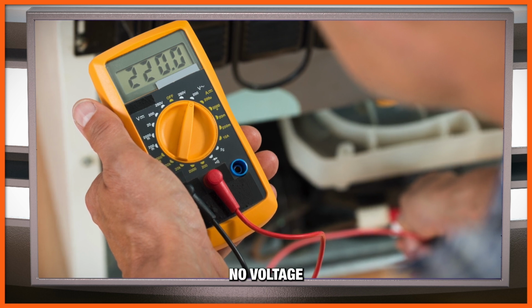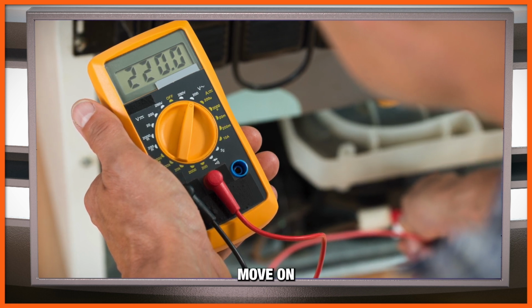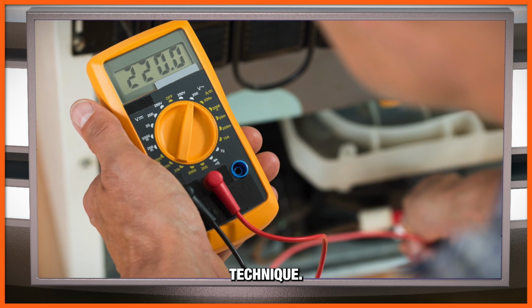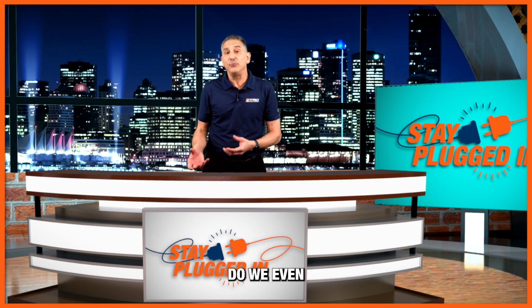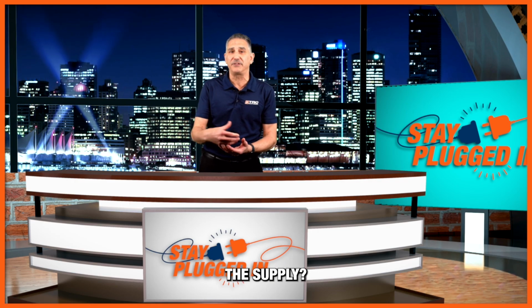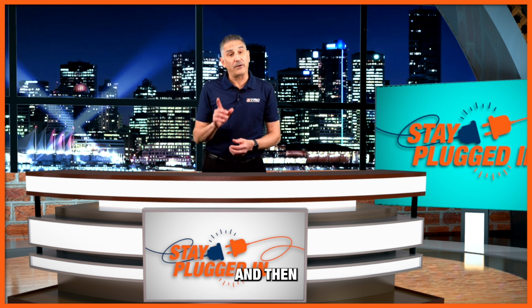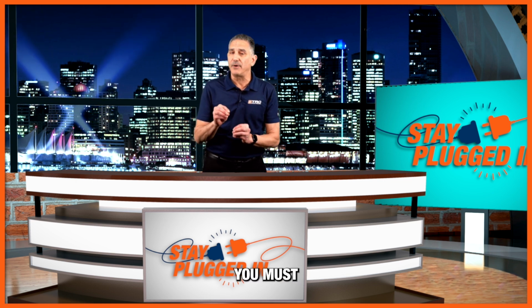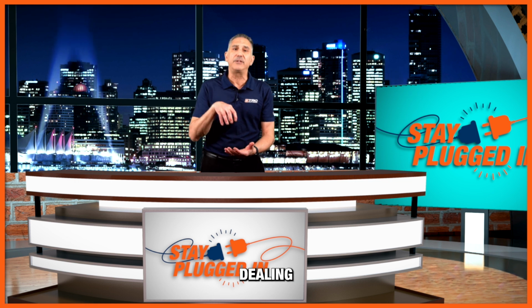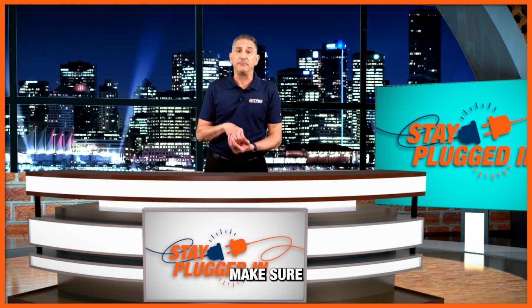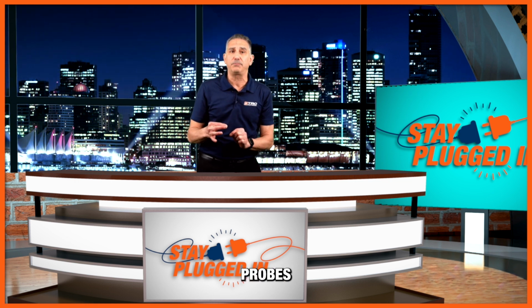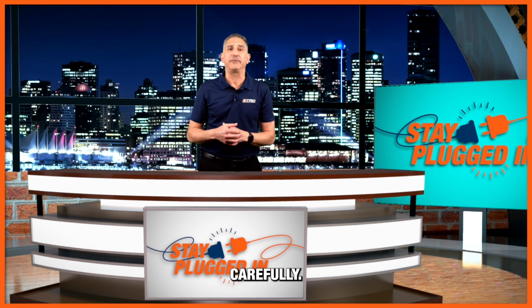If there's no voltage present, we move on to the next troubleshooting technique, where we verify whether there's even an AC input coming into the supply. A note here: proceed with caution, because now you're dealing with high voltages. Make sure you know exactly where to put those probes and measure carefully.